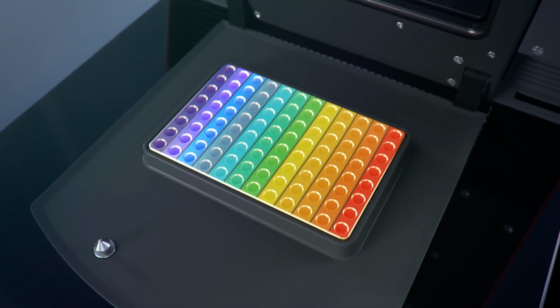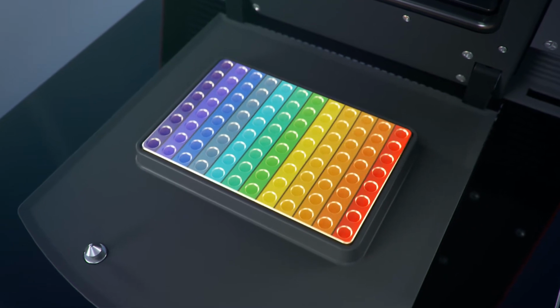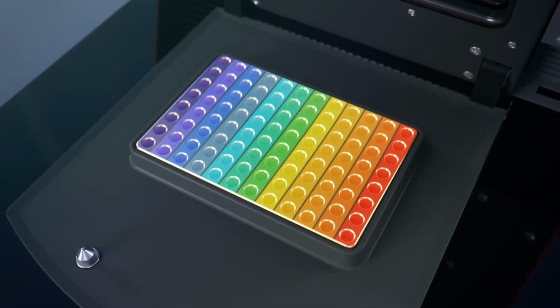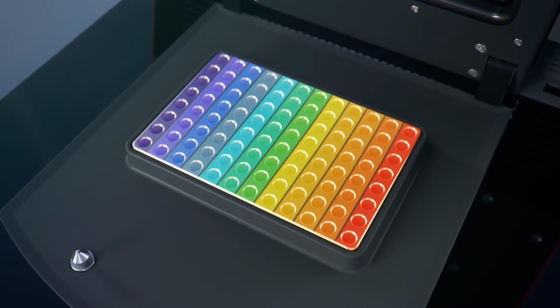With the linear gradient tool, users can enter integer temperature levels across 12 columns in a range of up to 40 degrees Celsius, eliminating guesswork for gradient applications.